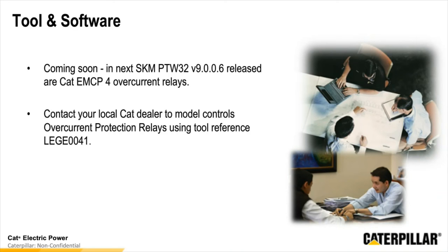So you'll be able to take the relay set points that we currently are talking about in the presentation today for the package. This will help with a lot of those decisions where customers are looking at and saying, do we want to remove the on-set or on-generator package breaker and move that off the package? You may be able to make those decisions by looking at the relay set points and doing your coordination a little tighter.